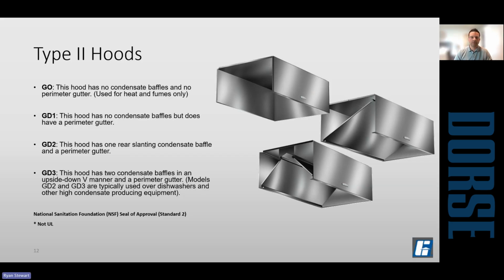So as far as type 2 hoods are concerned, these are 3 different configurations. The most common is going to be the one on the top there, just a standard canopy. It's going to have a full perimeter gutter with a drain. The other 2 have condensate baffles in there. When initially designed by manufacturers, they thought these would be good for high steam applications. It'll condensate on the plates, allowing us to remove more of that from the airstream.